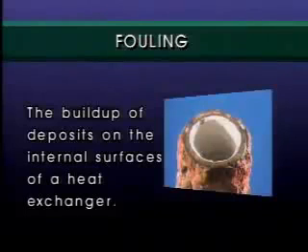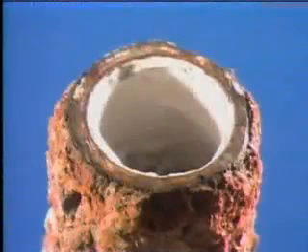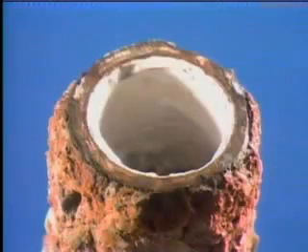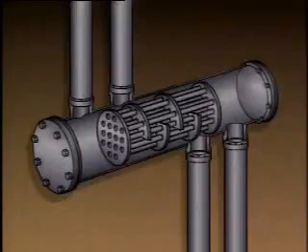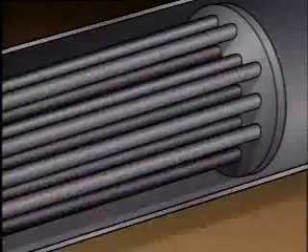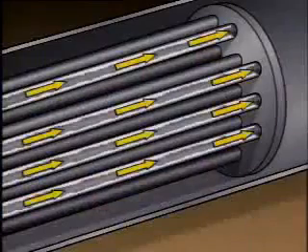Fouling is a term that's often used to describe the buildup of deposits on the internal surfaces of the heat exchanger. When fouling occurs, the result is an additional layer of material that heat must pass through. This additional layer reduces the ability of the unit to transfer heat. Also, if the buildup becomes excessive, the flow of fluids through the unit may be restricted. Fouling can be caused by many things. One common cause is impurities in the fluids passing through the heat exchanger.